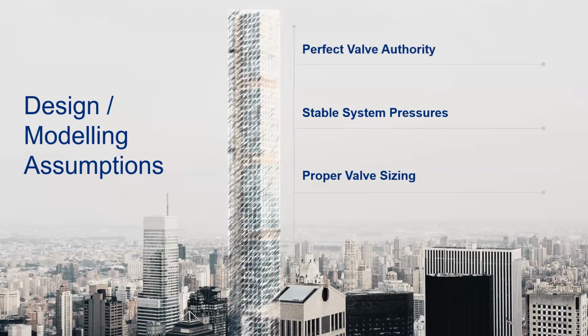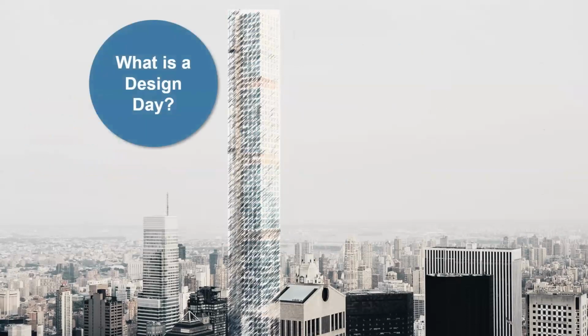We're going to start this off with a question to the group, and this is just a hypothetical question: what is a design day? Furthermore, traditional design processes are developed around this design day. A design day, of course, is the hottest day of the year, or the worst conditions that the building has to be able to overcome. Typically, they encompass only 3 to 5 days of the year and only about 3 to 4 hours of each of those days. So by that logic, the building is designed around a circumstance that is likely only to happen about 16 hours a year. What that equates to is 0.2% of the time of the year it's in a design condition. The rest of the time, everything is oversized.